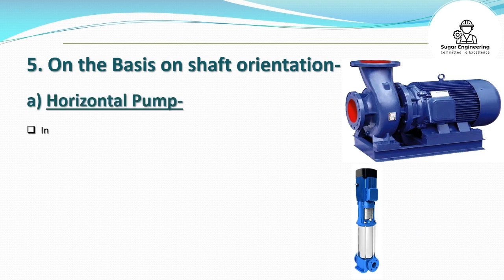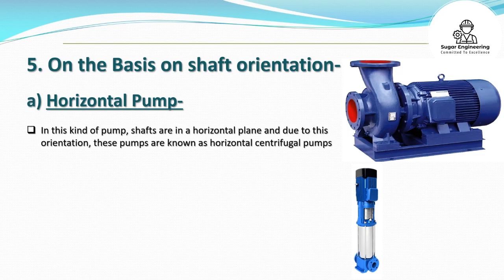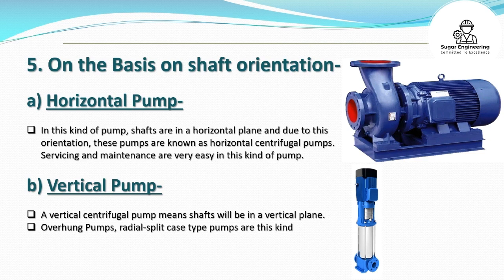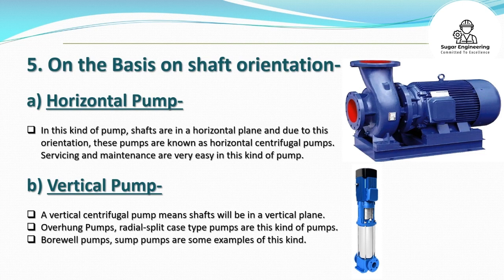On the basis of shaft orientation: A. Horizontal pump — in this kind of pump, the shaft is in a horizontal plane, and due to this orientation these pumps are known as horizontal centrifugal pumps. Servicing and maintenance are very easy. B. Vertical pump — a vertical centrifugal pump means the shaft is in a vertical plane. Overhung pumps and radial split case type pumps are this kind. Borewell pumps and sump pumps are some examples.